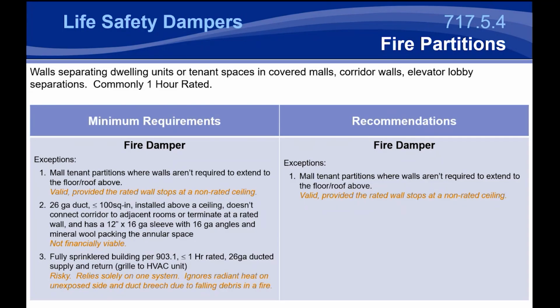There are some different exceptions here for these fire partitions, specifically when you're dealing with what's called a subduct. Now, the subduct has to be 26 gauge, it has to be relatively small, so 100 square inches or less, and it has to have a 16 gauge sleeve with 16 gauge angles, and it has to be protected with mineral wool around the annular space between the subduct and that smaller duct inside. This doesn't really make sense financially. Your damper is going to come with mounting angles that, for this size, may very often be less than 16 gauge. Also, it's really not that much cheaper to install this compared to a traditional curtain style fire damper.